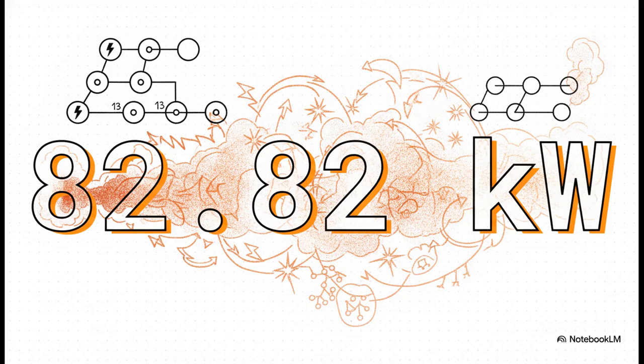Let me show you exactly how bad a bad guess can be: 82.82 kilowatts of total power loss. In a standard test of a 15-bus grid network, if you just guess and improperly place a 1.2 megawatt generator at a random location called bus 13, the power losses across the grid actually skyrocket to nearly 83 kilowatts.